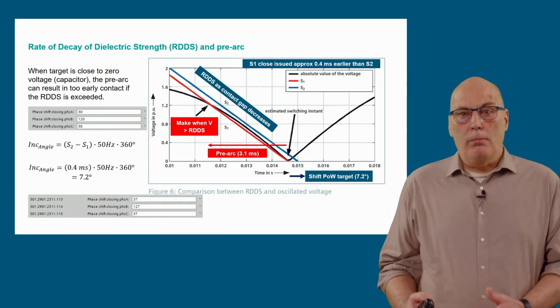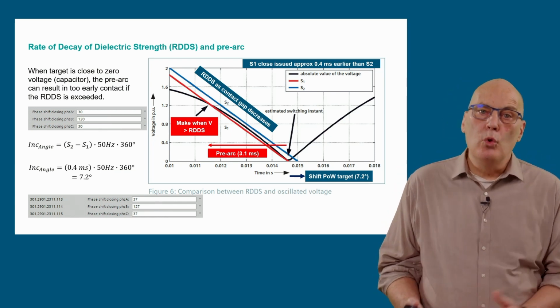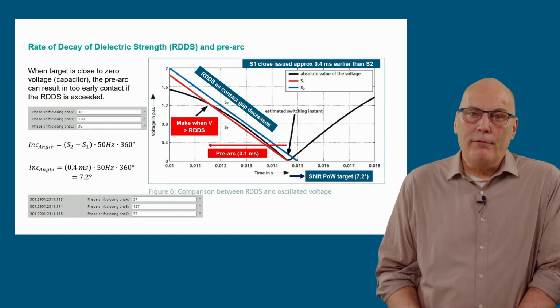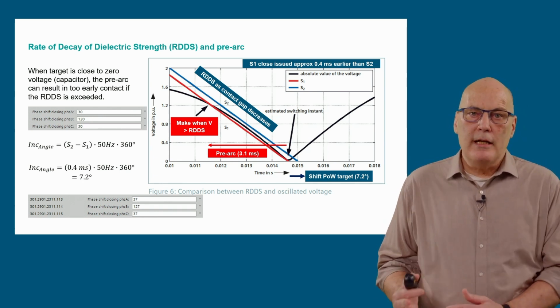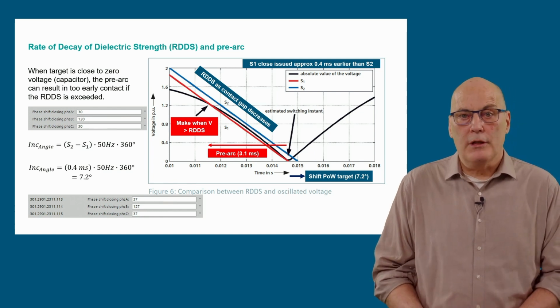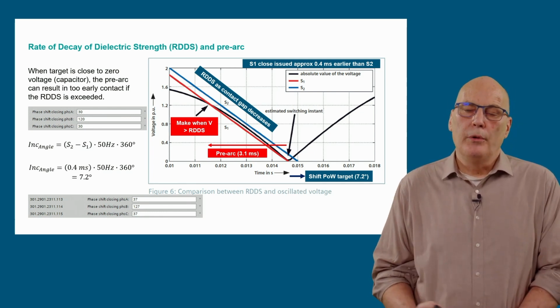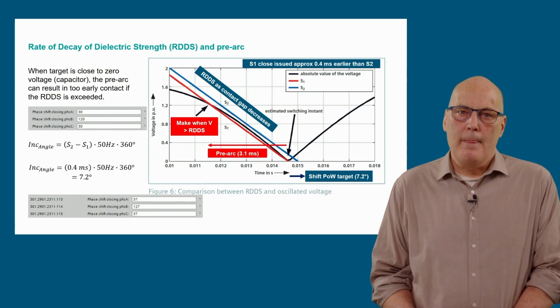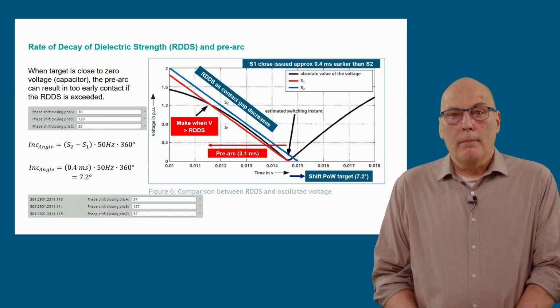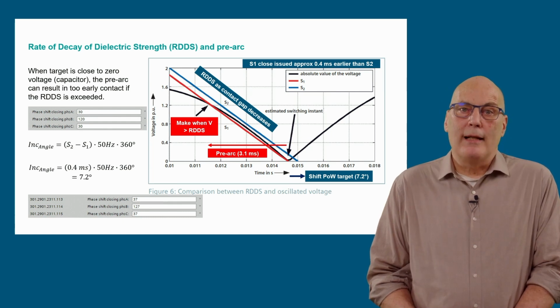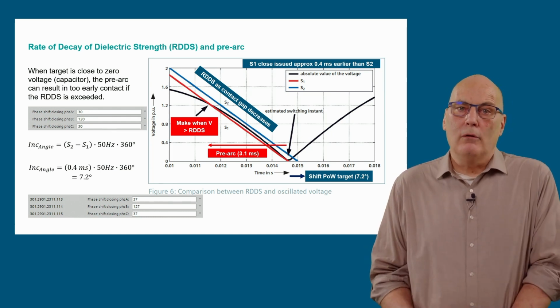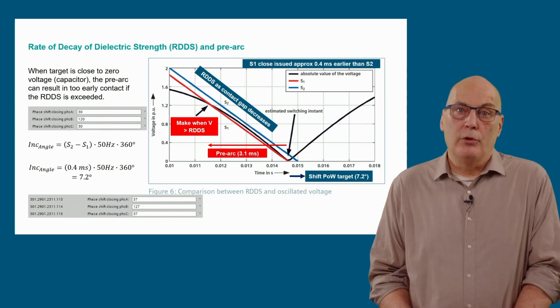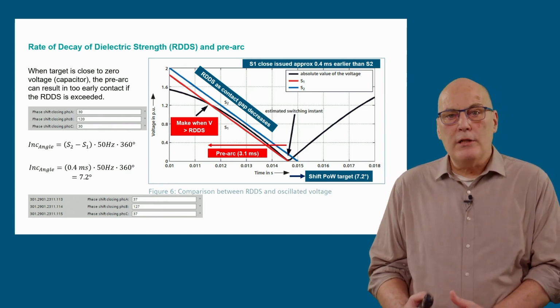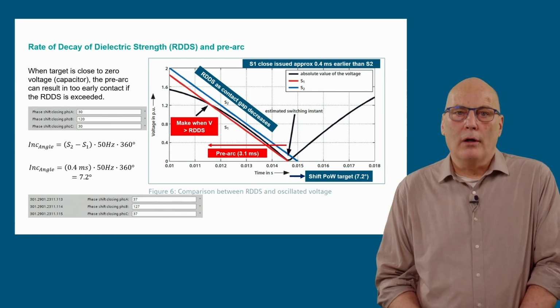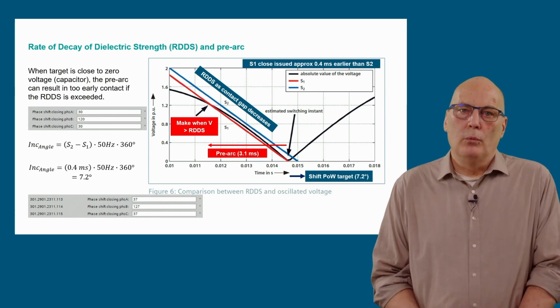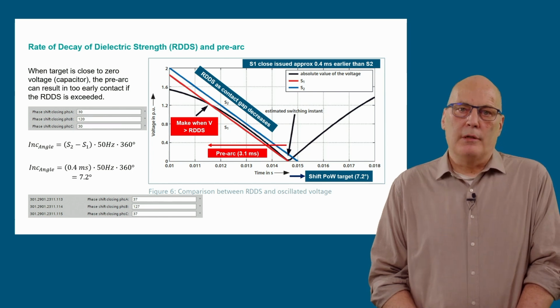To compensate for this problem, the target switching instant can be moved to slightly after the zero crossing, so that instead of using S1, which is near zero crossing, we move the target to S2, which is 0.4 milliseconds later. The equation shown here shows how the 0.4 milliseconds later target is converted to an angle of 7.2 degrees at 50 Hz. By increasing the set closing angles accordingly, the target closing is shifted to S2, which can prevent the much too early closing of S1.